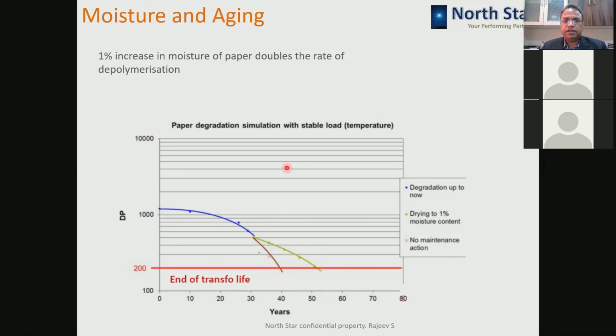So if you are maintaining the lower temperature and lower moisture, the rate of aging will be slow. And if you are not doing that, then the aging will be faster. So a normal transformer, if not maintained well, then probably this graph will come. But if you maintain the moisture less than 1%, then your transformer life can be extended by another 10 to 15 years.